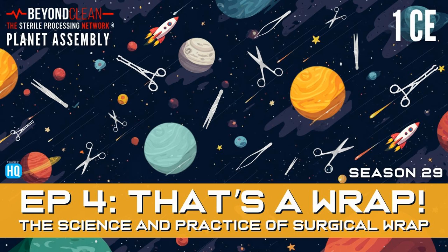So that's why you next have to focus on material strength. And that's both in the machine and the CD direction. And that just means it needs to hold up against tearing, puncturing, no matter how it's handled. But then you say, okay, well, material strength is one factor, but you just can't have a strong wrap and it does not allow the steam to penetrate through. Well, that leads to the property of porosity, right? It needs to be just right. This speaks to the wrap's ability to let sterilizing agents like steam or gas, ethylene oxide, in, but block the contaminants from entering into the sterilization wrap.